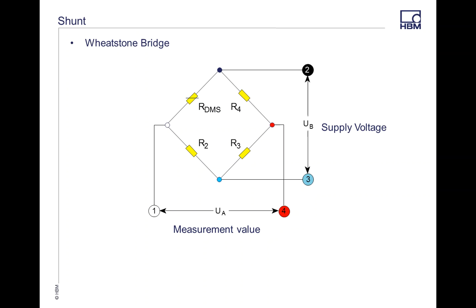Here's a quick example of a Wheatstone bridge. All of our torque transducers are Wheatstone bridge strain gauge based. Basically, there's a resistor set. Two of the bridges have supply voltage. The other two are set up for measurement voltages. So as it comes in, it calculates the resistance on the measurement.